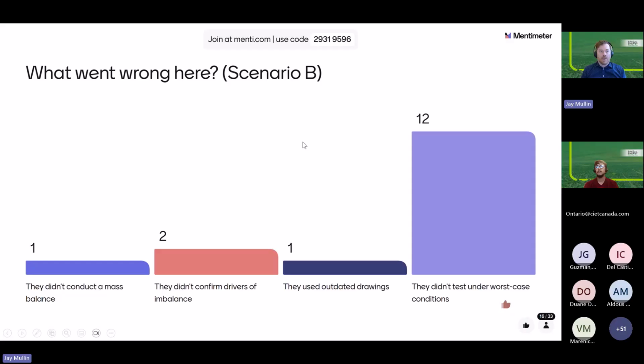So the situation in January, when they were getting the complaints, outdoor air percentages and different things like that can change. They might be minimizing outdoor air, but still having a lot of exhaust happening. By the time they got around to doing the study, it was in the spring, and then they implemented stuff in the summer. So it could be that their operations in January in the winter represent a kind of worst case scenario in terms of imbalance that the study didn't pick up on and that the solution didn't address.